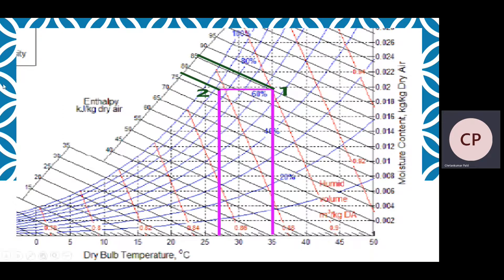The enthalpy in kJ per kg of dry air is read from the inclined lines on the psychrometric chart, marked 65, 70, 75, 80, 85. We draw lines parallel to the enthalpy inclined lines passing through point 1 and point 2. The green line through point 1 intersects above 84, giving H1 equal to 85.4 kJ per kg of dry air. Similarly, H2 is equal to 77 kJ per kg of dry air.